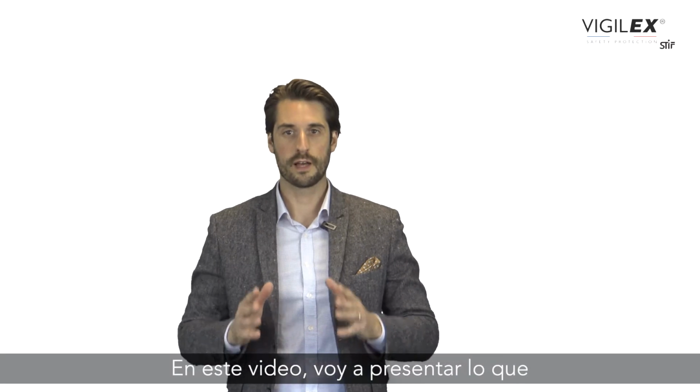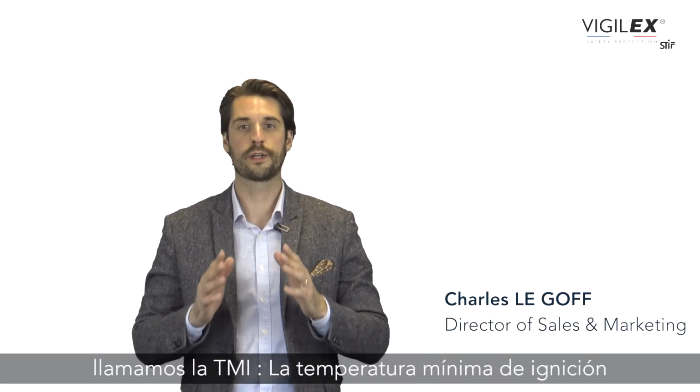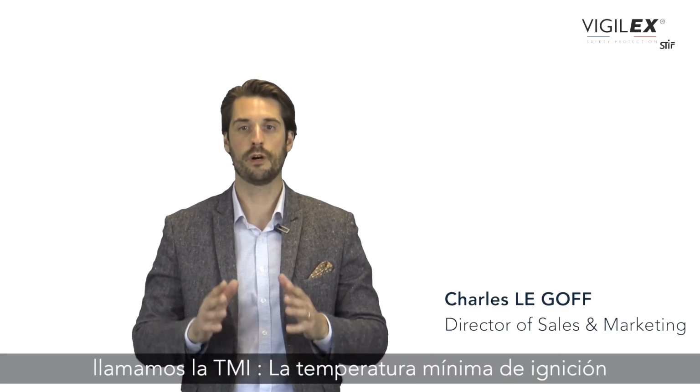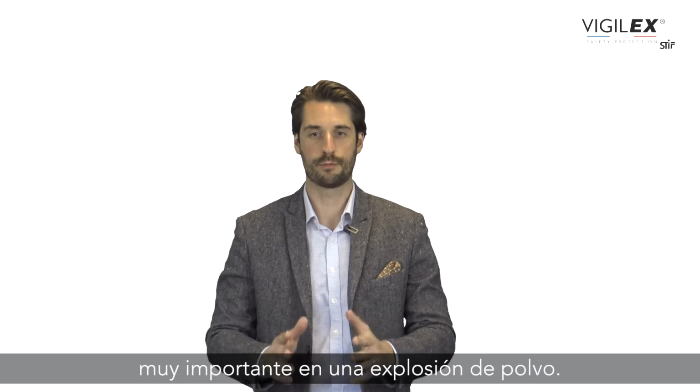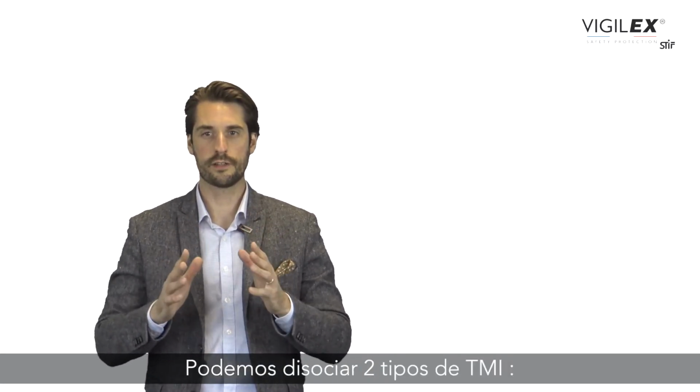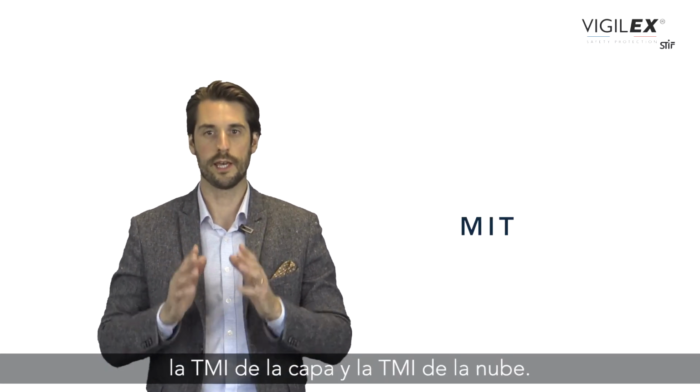In this video, I'm going to present what we call the MIT, the minimum ignition temperature. This feature has a very important influence on a dust explosion. We can dissociate two kinds of MIT, the MIT layer and the MIT cloud. Let's start with the MIT layer.